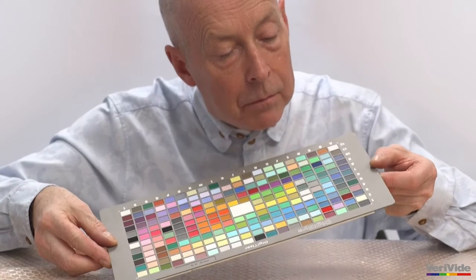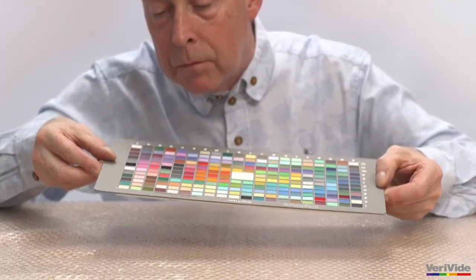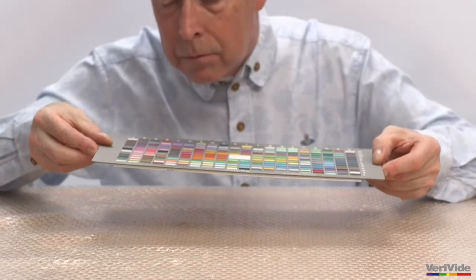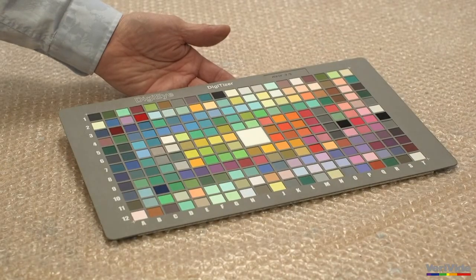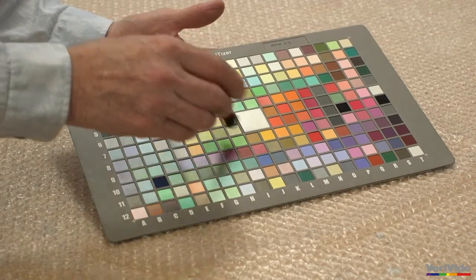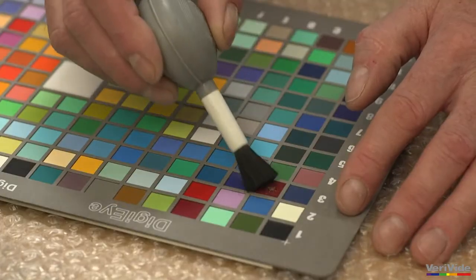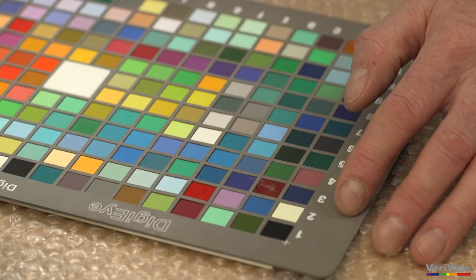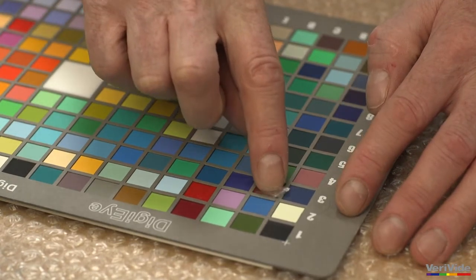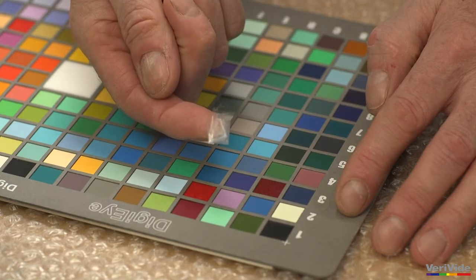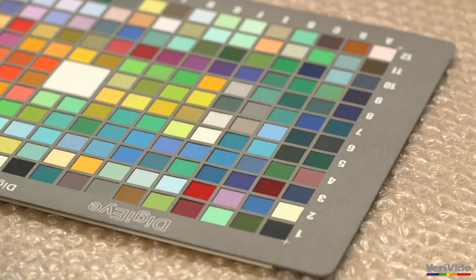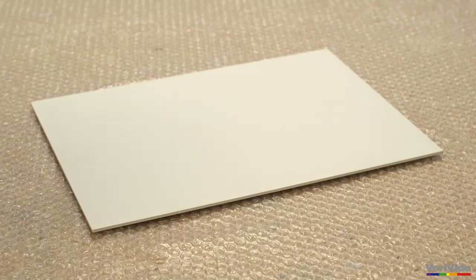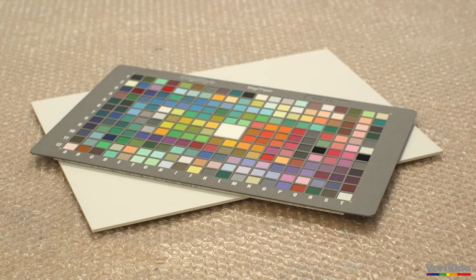The Digitizer chart contains 240 patches of colour. These are a mix of squares of printed paper, textile felts and special plastics. Occasionally, the textile felt samples will pick up dust, and these can be simply cleaned by a light brushing off. For stubborn dust, you can carefully pick off using a small piece of sticky tape. Be very careful to keep tape away from printed paper swatches to avoid damaging the printed paper finish. Any damage to any square will render the calibration chart out of service, and this should be replaced as a matter of urgency in order to maintain the accuracy of the system.